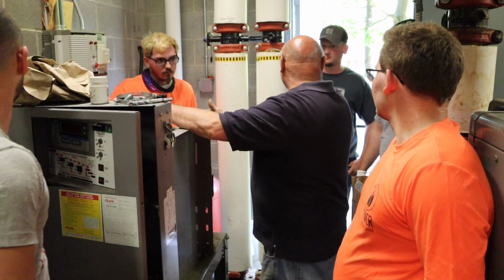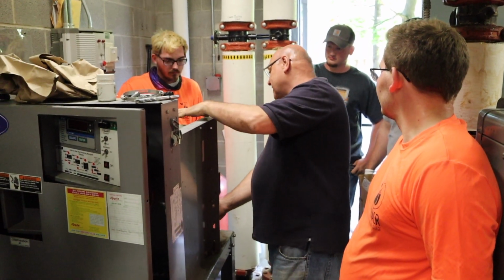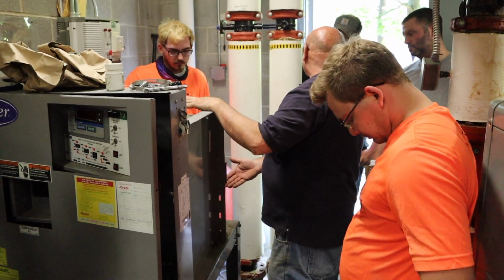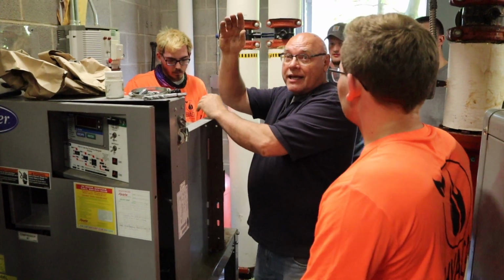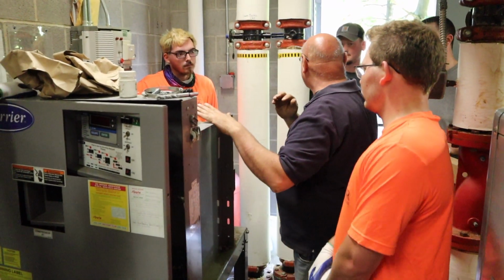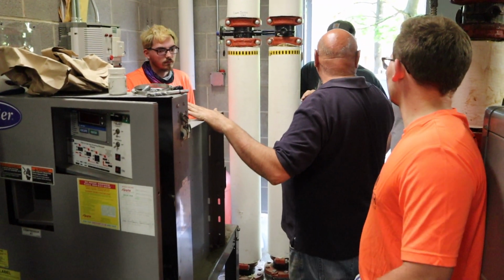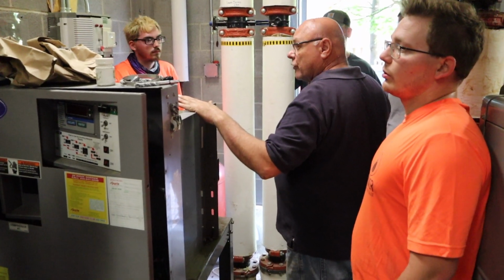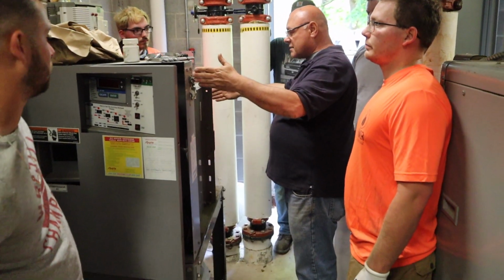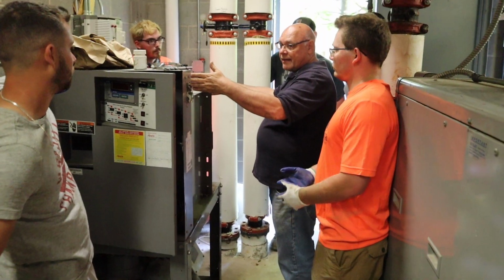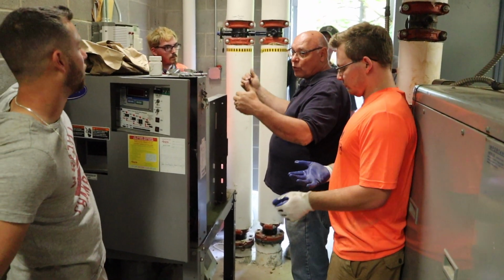We're going to be making 47-degree water right in this spot, and then that's going to send out to every single room in the building. Via air handler, with VAVs? No, they're actually wall units that work off either hot water or chilled water.